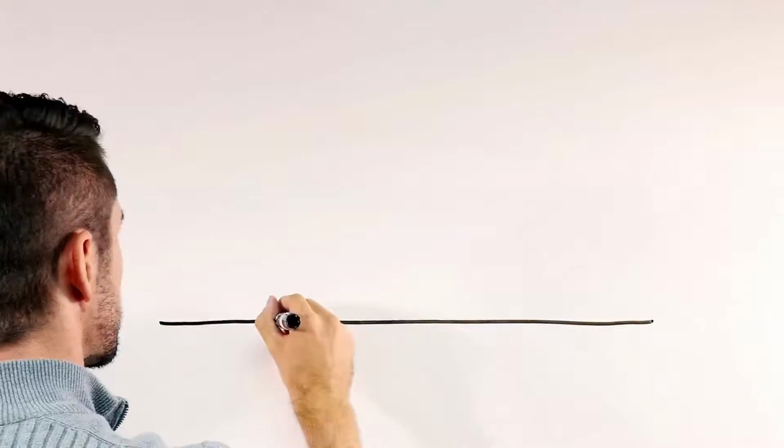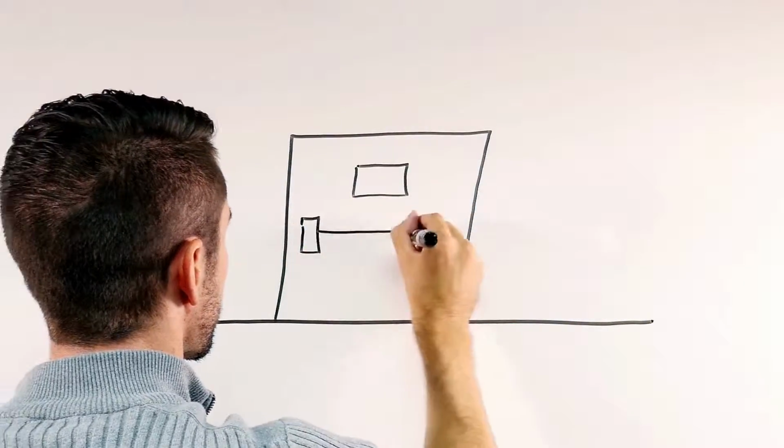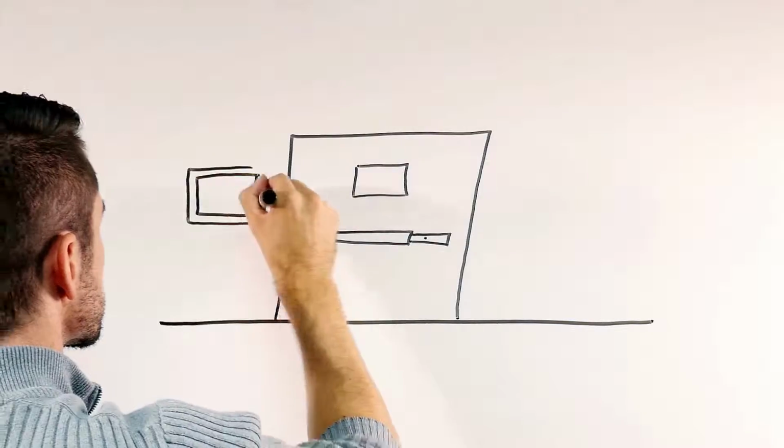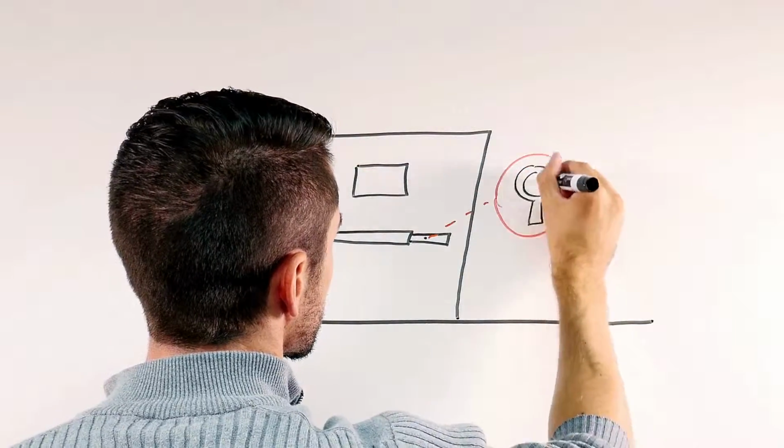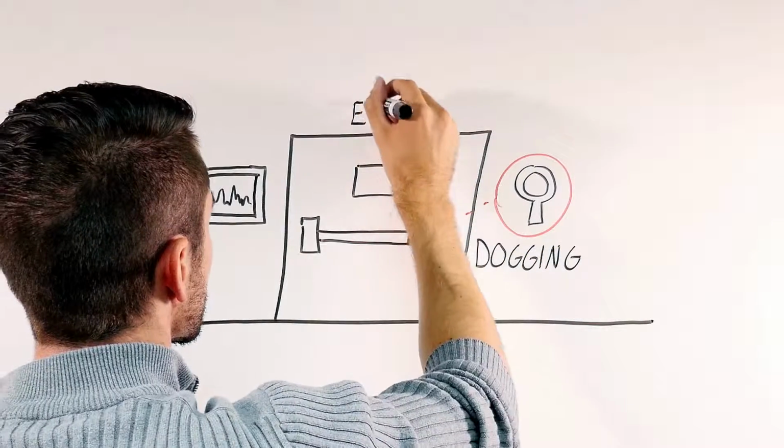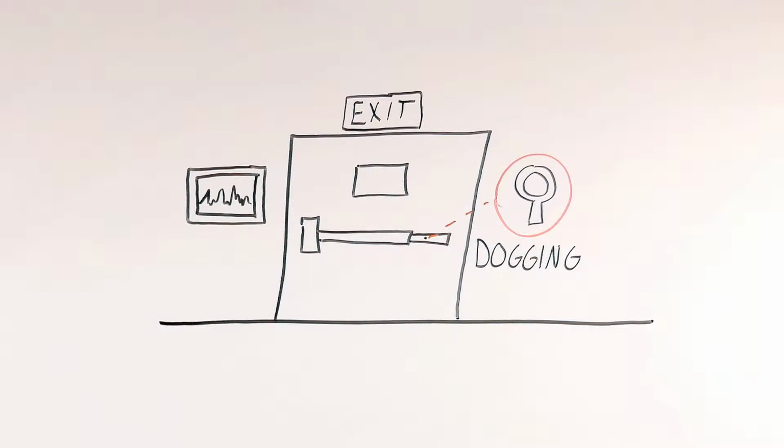The dogging feature, which allows the latch to be manually held retracted, is not supplied on fire exit hardware because fire doors must have an active latch bolt to keep the door closed and latched during a fire. Electric latch retraction may be used to electrically dog the latch on fire exit hardware, but the latch must project automatically upon actuation of the fire alarm.